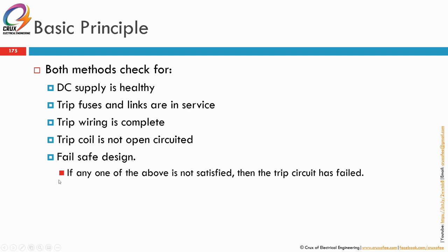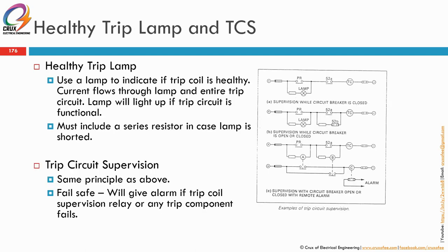And also this is a fail-safe design. If any one of the above is not satisfied, then the trip circuit has failed lah. So if any one of these fails, the trip circuit supervision will not light up or will de-energize lah. So you know that there is something wrong that you must check in the trip circuit. Trip circuit supervision is a little bit confusing. So let's see. Healthy lamp, trip lamp and the trip circuit supervision.